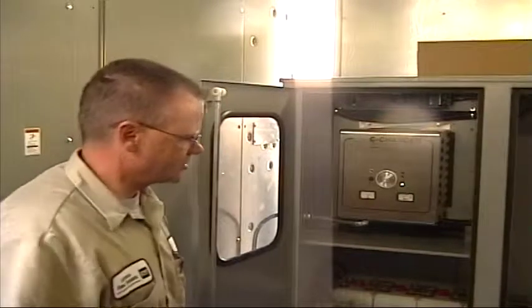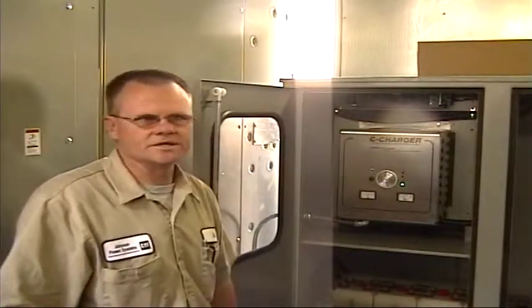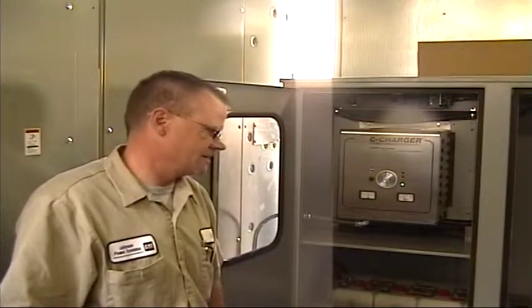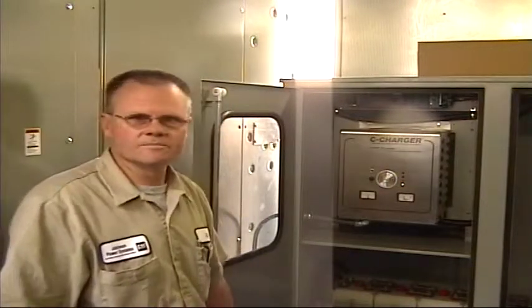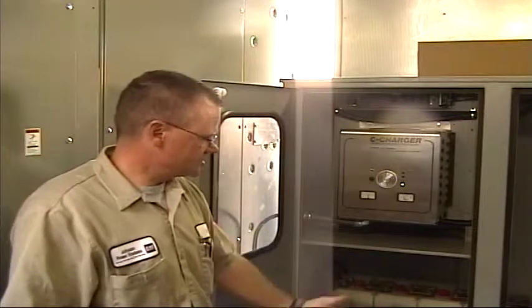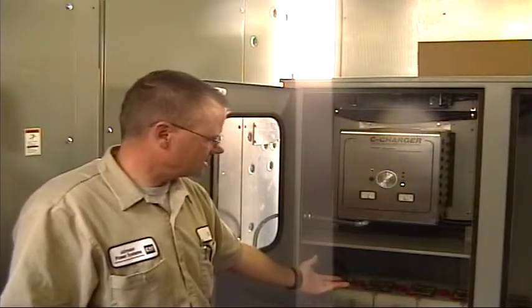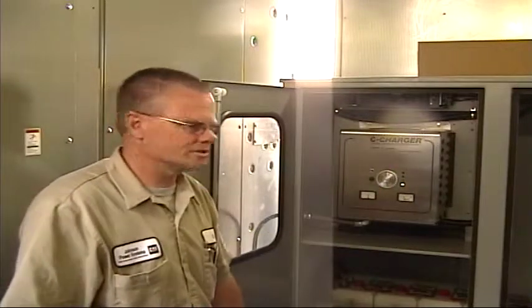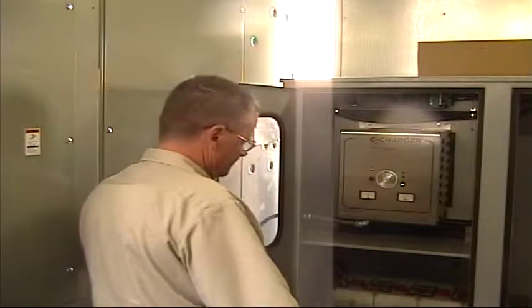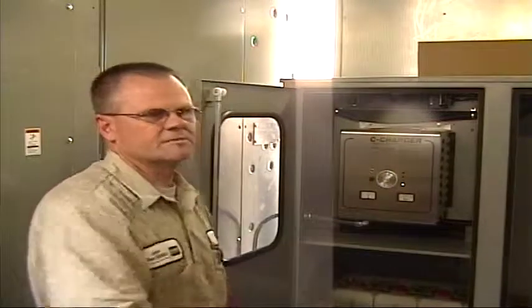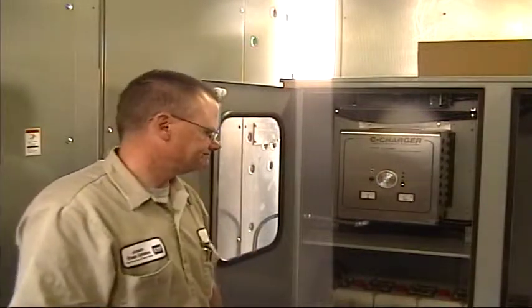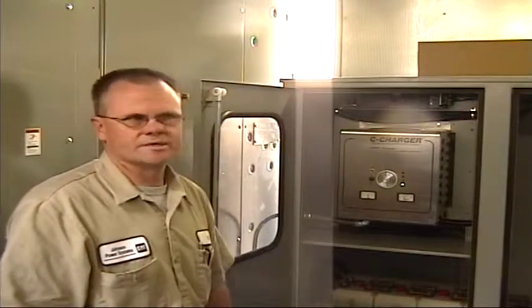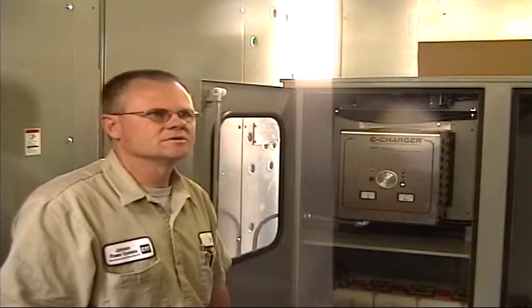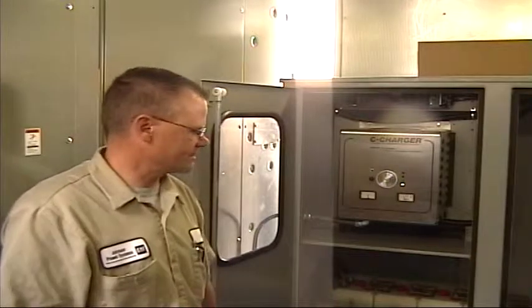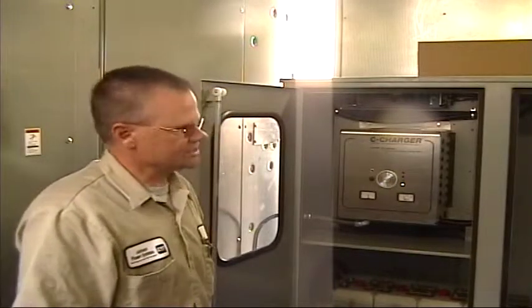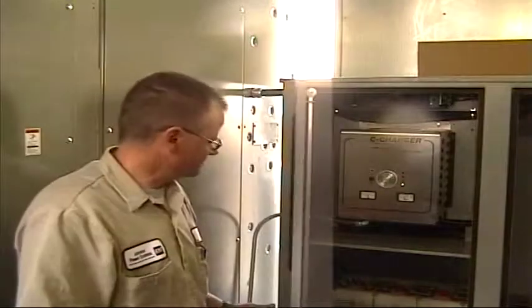You guys have the maintenance book on this. NiCads are pretty maintenance friendly, that's why I believe they're respected, they don't require a whole lot of maintenance. So I would do a visual, make sure you don't have corrosion showing, monthly or whatever your normal inspection is. Make sure the water levels, they're visual, you can see them if one's going down. That's about it, follow the maintenance recommendations for that manufacturer in your handouts, because I'm not too sure on exact maintenance intervals on those. But that's what these will do. So again, that's a pretty important part of your system.